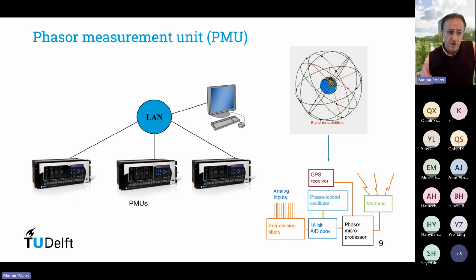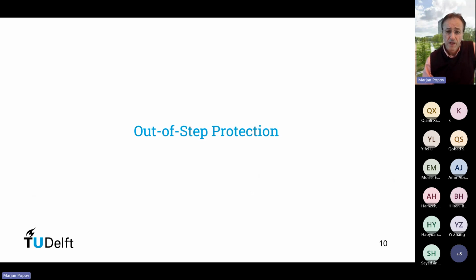Wide area monitoring protection is realized normally by synchrophasors. We call them also phasor measurement units, and they are being used in a way that they are synchronized with GPS. They provide real-time measurement values of voltage and current phasors, frequency, and the rate of change of frequency, which are transferred normally to the desktop computer where the algorithms operate.